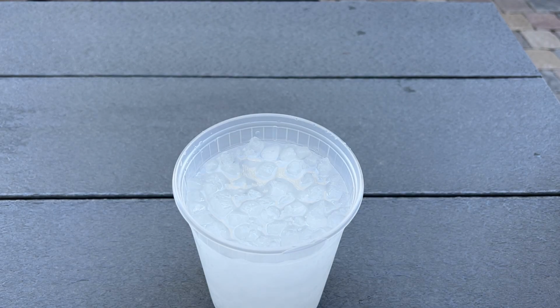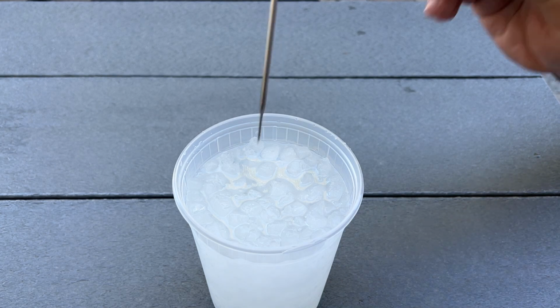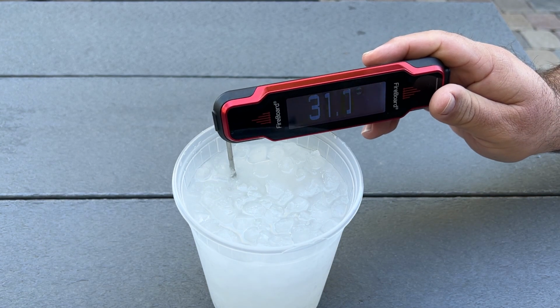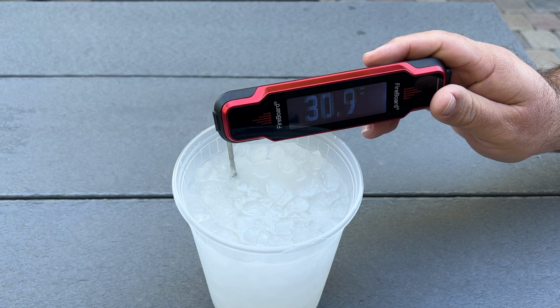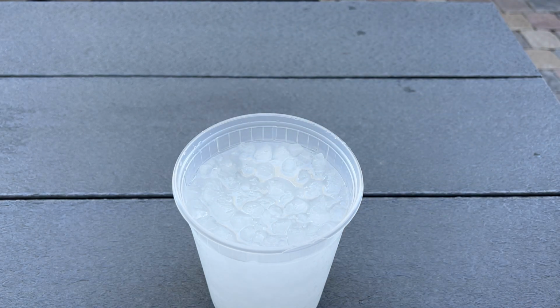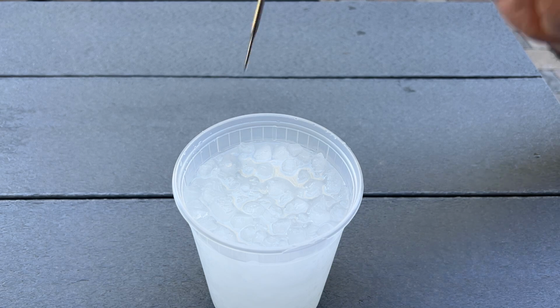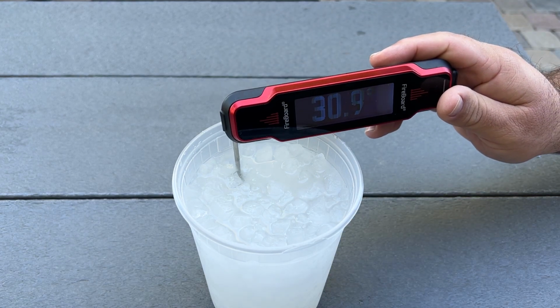First, we timed how long it would take to read 32 degrees in a cup of ice water. We filled the cup with ice, then added water and stopped before any of the ice floated, giving us a bath of water that will measure 32 degrees Fahrenheit. We dropped the probe in, and it read within half a degree in exactly 1 second.